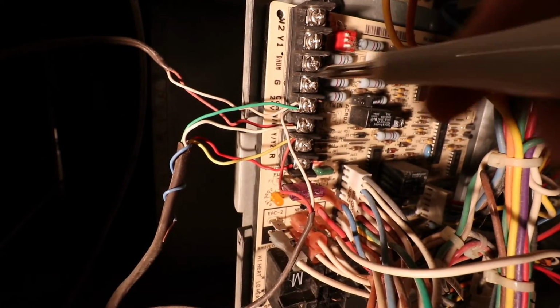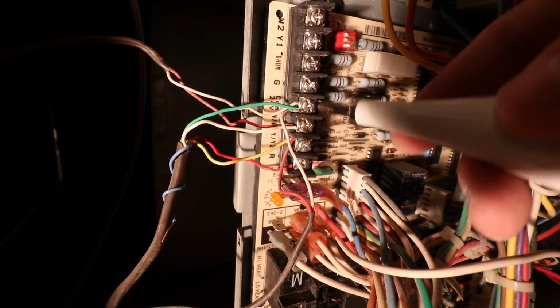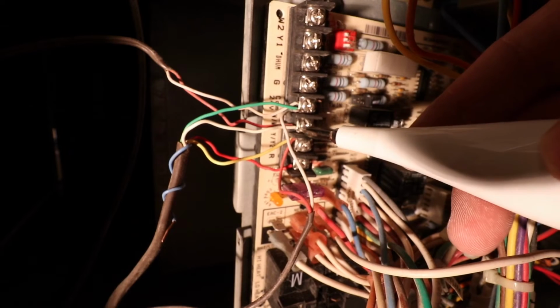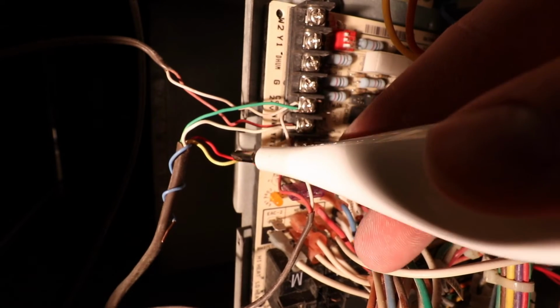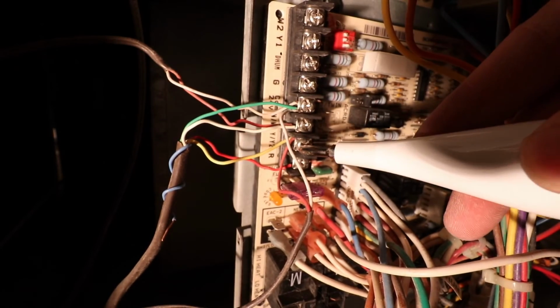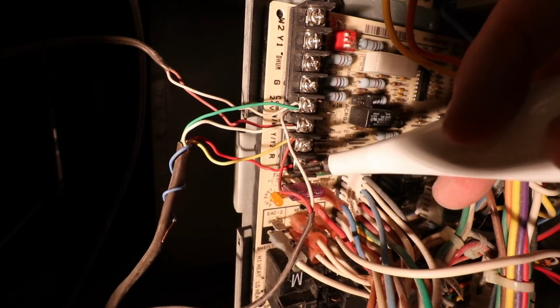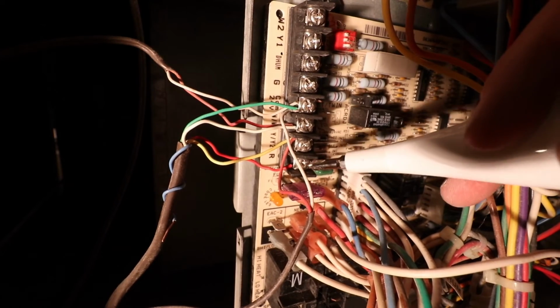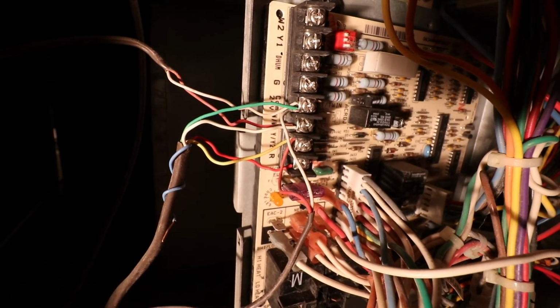So now we've got our green wire on the common wire. We still have our white wire going to the W terminal, that's our call for heat. We've got our yellow wire, that's our call for air conditioning, on the Y terminal. And we've got our red wire, which is the power wire, connected at the R terminal.